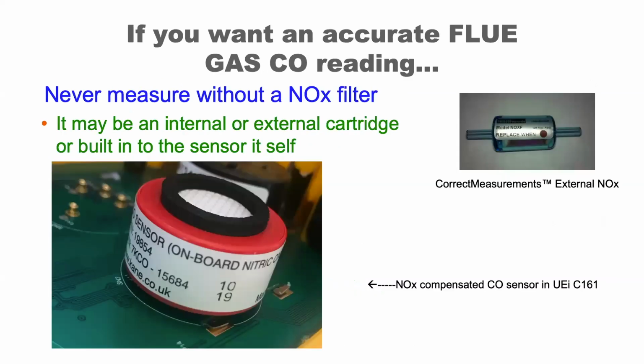So if you want an accurate flue gas reading of CO, you should never measure without a NOx filter. This may be an internal filter on the sensor. And in fact, this one is the NOx compensated CO sensor in the UEi C161 that I took apart a couple weeks ago. You can see right on the label, onboard nitric oxide filter. Or it could be an external cartridge that's added on to the sampling hose.